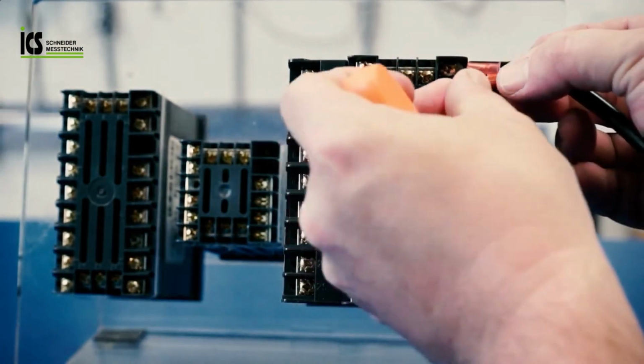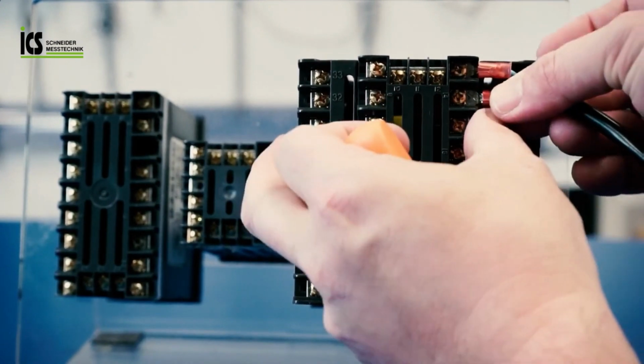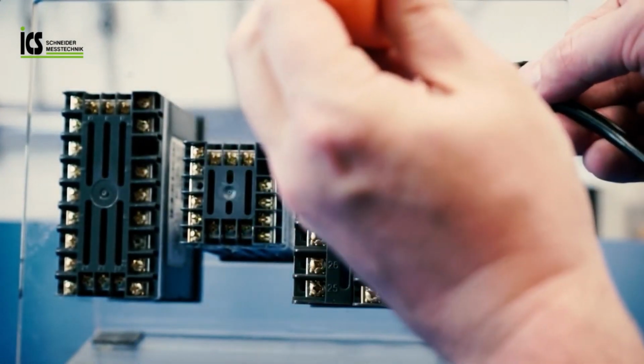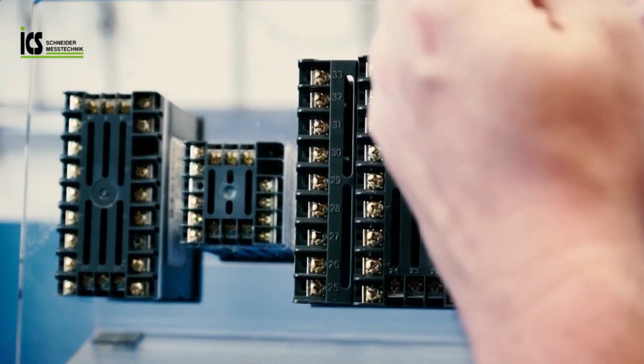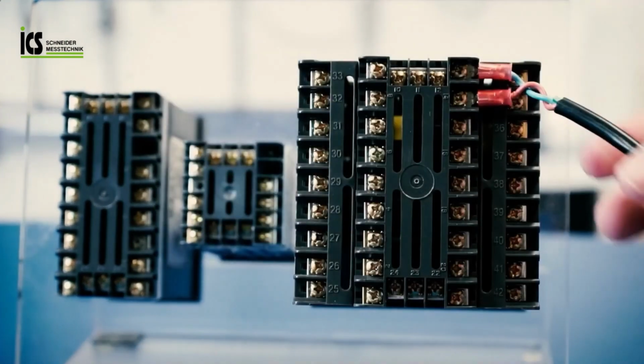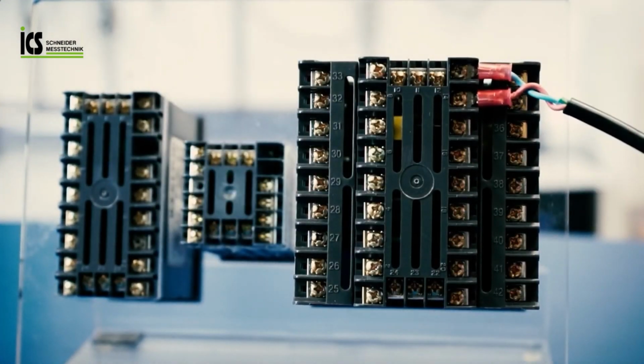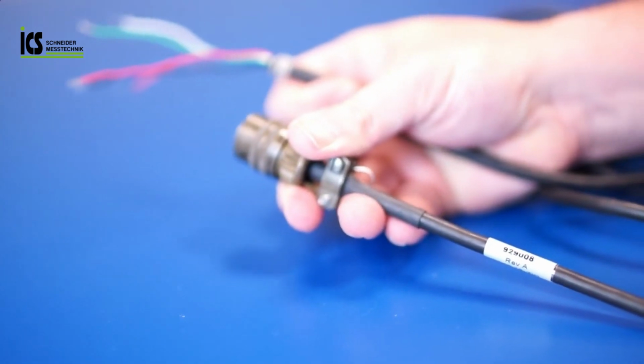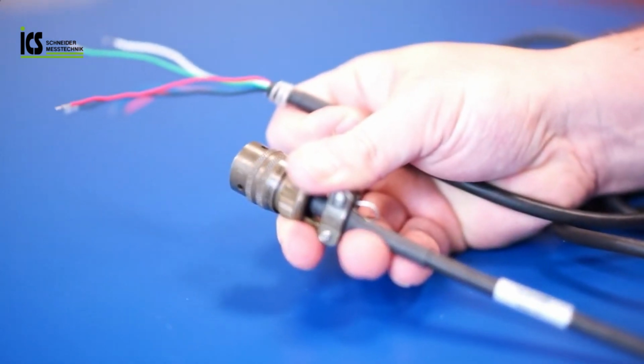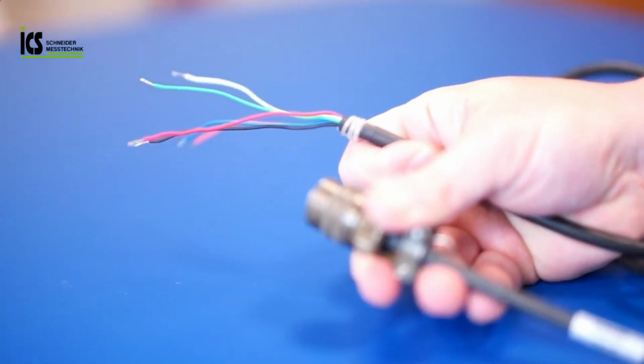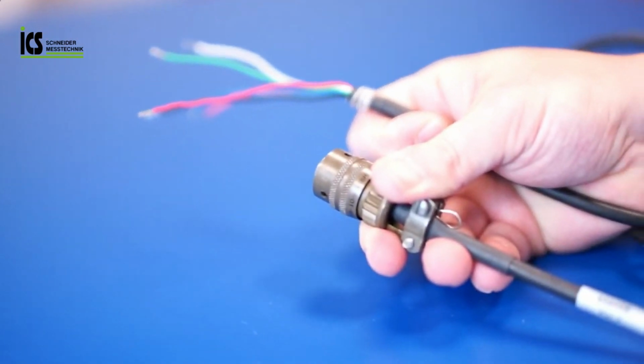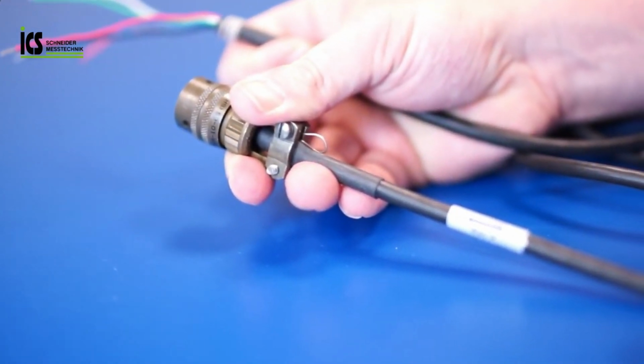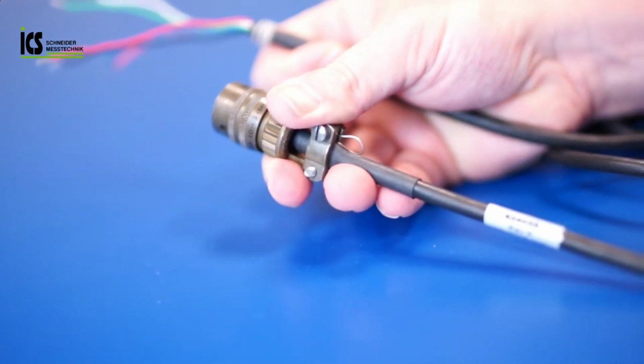There is no reason to power up the instrument in this step. Power should be supplied after the sensor cable has been connected to the instrument and there is no operator exposure to the screw terminals. With the cable assembly in hand, the bare wires are terminated to the instrument based on the signal output of the pressure sensor. In this example, our pressure sensor has a 0 to 33.3 millivolt output and will utilize all 6 wires.